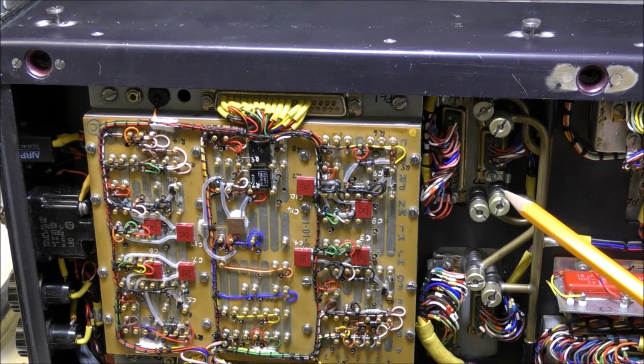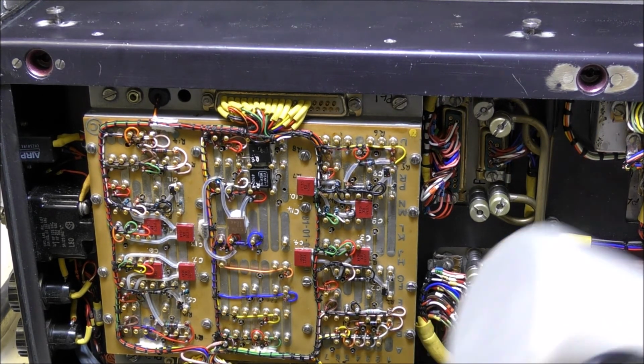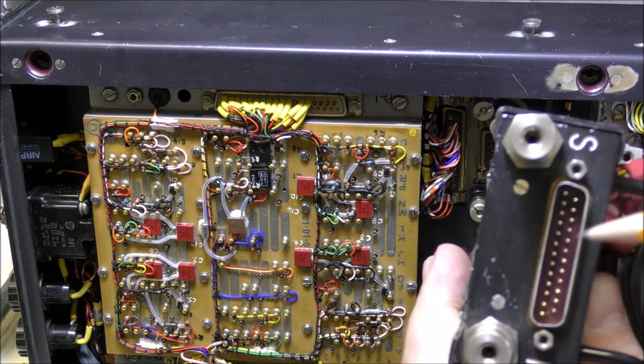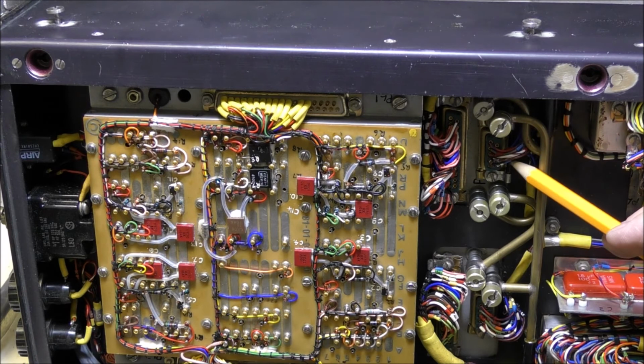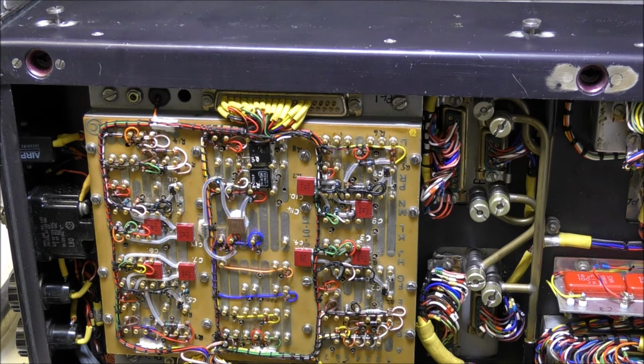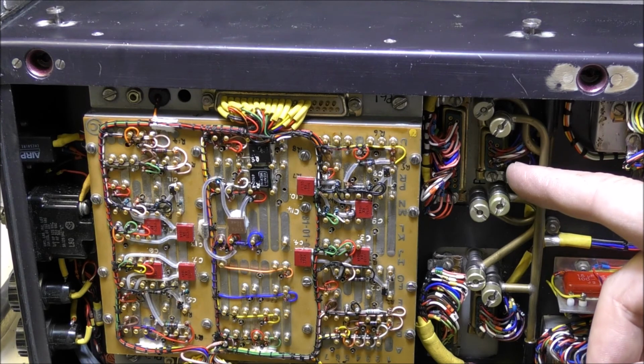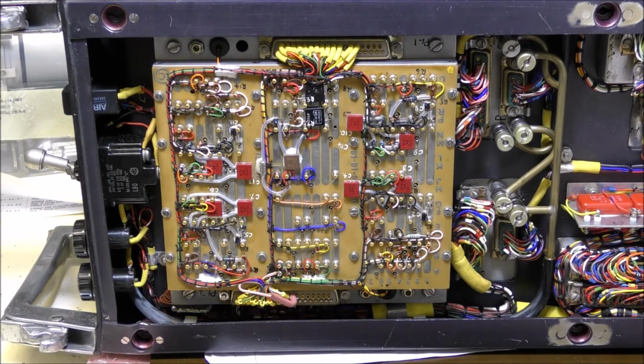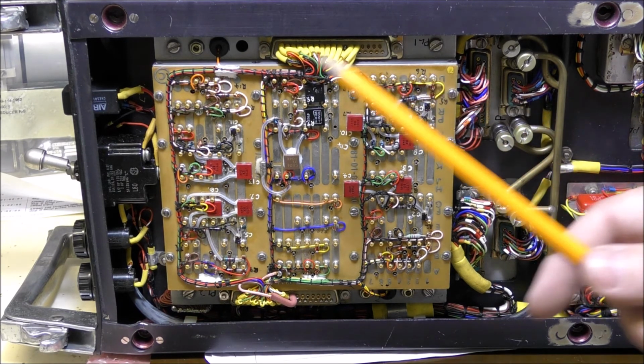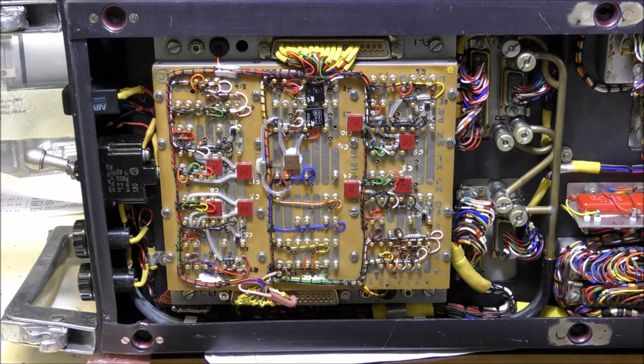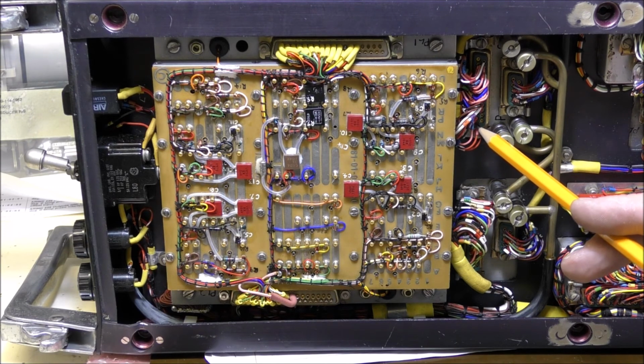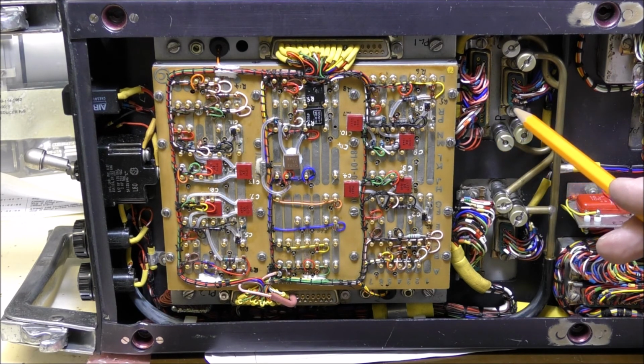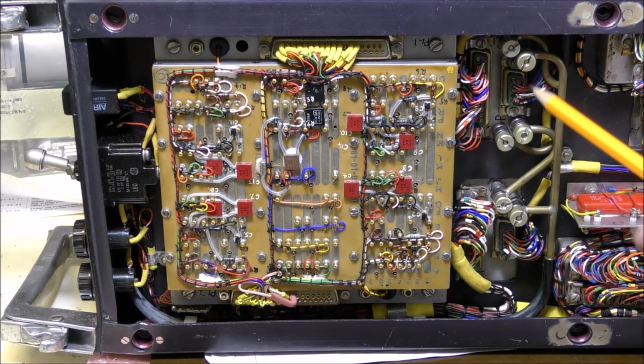I don't know the purpose of this sub-D9 connector here, because on this instrument there is only this 25 pins connector here. So this is maybe a calibration stuff. It can be interesting to remove the module and to see what is connected on this socket here. This is very complicated. It is not possible to remove the module actually, because it requires removing everything here. And this is absolutely impossible. So I just found that there is a connection between one terminal of the excitation coil and one terminal of this connector here, but it doesn't help.